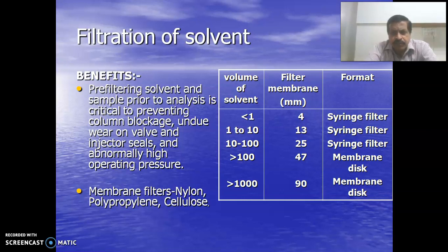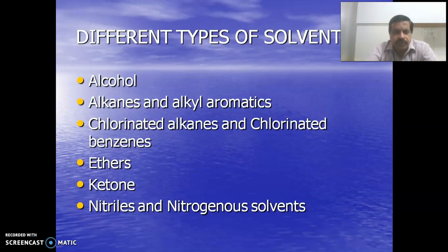Then filtration of the solvents uses different filters. You can use a syringe filter, with variation in the membranes. Pre-filtering the solvent and sample prior to the analysis is also critical to prevent, as I briefed earlier, column blockage and undue wear, and there is a possibility of nylon membranes being used for solvent filtration.